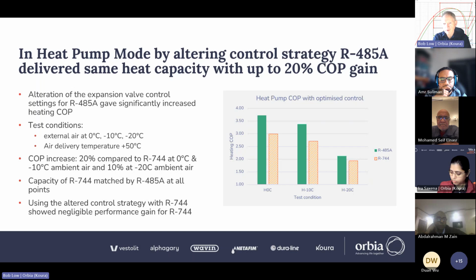And the 3 points here are 0C, -10C, and -20C. And at the first two temperatures, 0C and -10C, we had 20% COP gain. And at the lower temperature, we had 10% COP gain. And we expected the COP gain. We were pleasantly surprised that the COP gain maintained even down to -20C. And in these points, with the same delivered heating capacity.